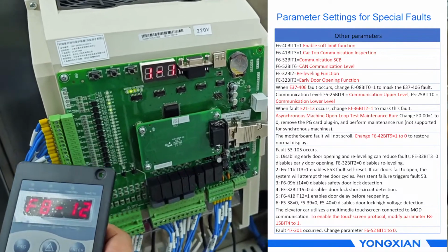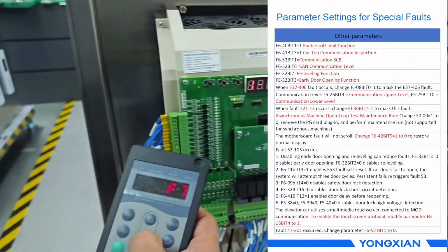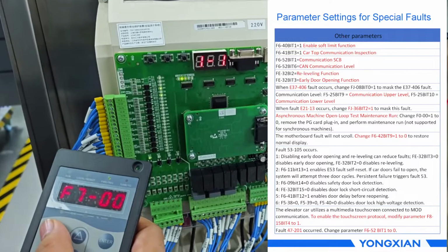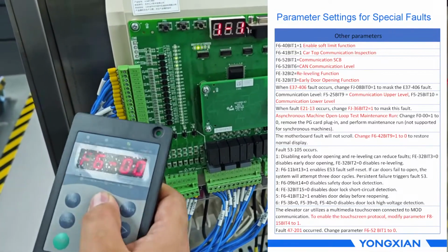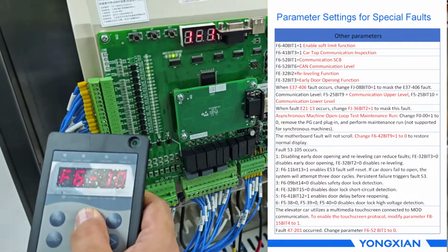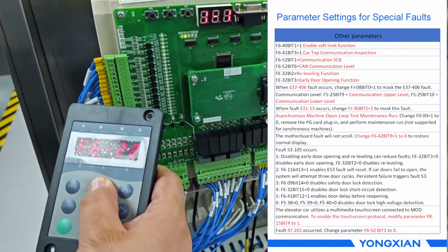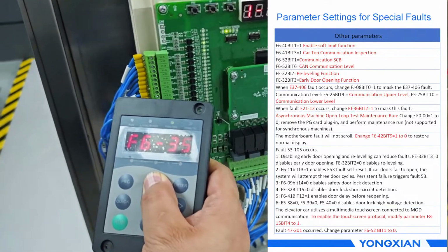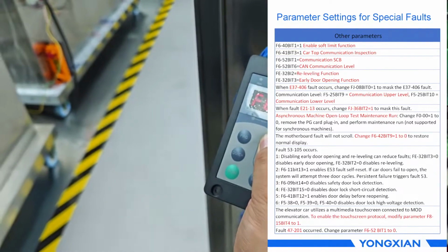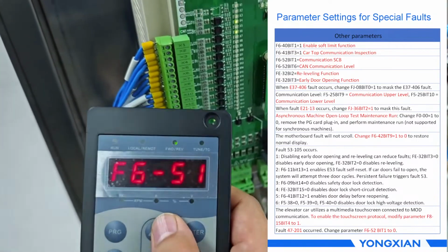When fault 47-201 occurred, change the parameter F6-52 bit 1 to 0.